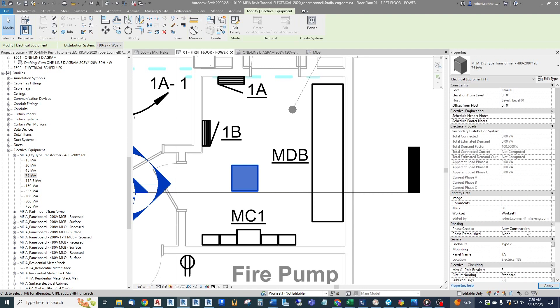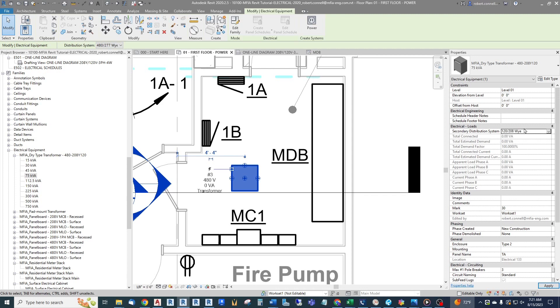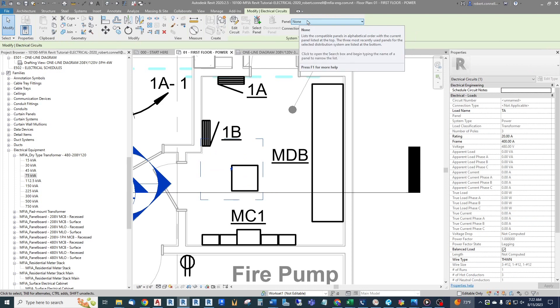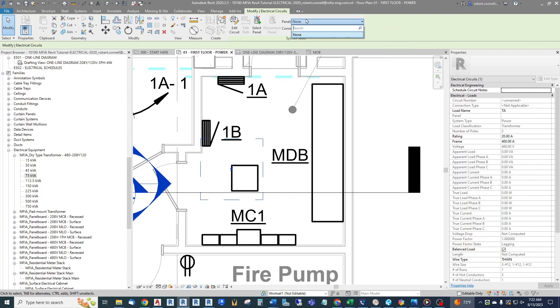To find the secondary distribution system, go up under Electrical to Loads — it's labeled Secondary Distribution System and hides right there. You can see no secondary distribution system is selected. Click on it and you'll see choices: 120/208Y is what we want. You could also select 120/240 single-phase or 480/277Y for an isolation transformer. In our case we want 120/208Y for the secondary distribution system. Without that selected you will not be able to connect anything to the secondary of this transformer. Then to circuit the primary, click on it, hit Power — this connects the transformer upstream to its primary source. We have no available 480-volt panels in this project, but that's how you'd connect the primary.